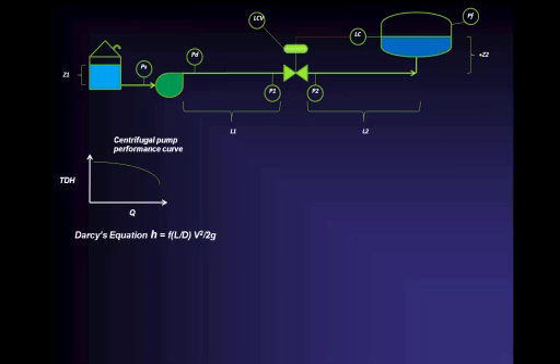We need to do a hydraulic balance, so we need to know how much pressure created by the pump is eaten up due to friction in the piping system. You can see I've labeled two pieces of pipe up there, L1 and L2. I need to know how much pressure I lose in those pieces of pipe. The equation that's used to do that is called the Darcy equation. It is that the head loss equals F, a friction factor, times L over D, that's an equivalent length of pipe, times the velocity squared of the fluid in the piping system, again divided by 2g, g being the gravitational constant, 32.2 feet per second squared. H is measured in feet.